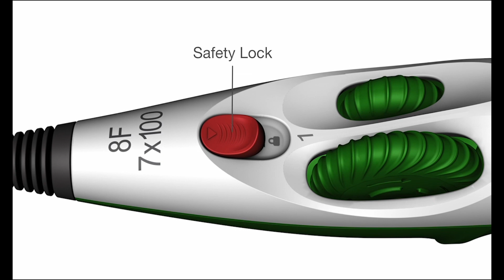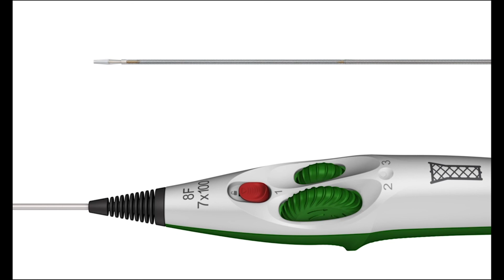A red safety lock on the handle is designed to prevent the operator from prematurely deploying the covered stent and must be switched to the unlock position when ready to deploy. The handle includes 2 deployment thumb wheels. Activating the large thumb wheel retracts the delivery sheath to deploy the covered stent slowly. The operator has the option to switch to the small thumb wheel and deliver the covered stent more quickly.